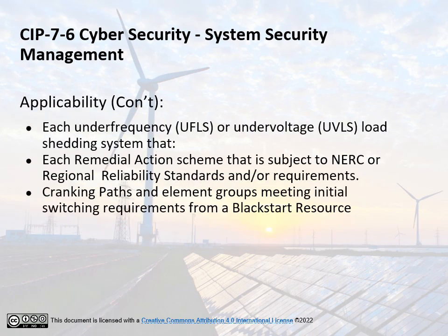CIP-007-6 System Security Management. Continued applicability: Each under-frequency load shedding (UFLS) or under-voltage load shedding (UVLS) system that is subject to NERC or regional reliability standards and/or requirements and performs automatically under a common control system without human operator initiation, of 300 megawatts or more. Each remedial action scheme that is subject to NERC or regional reliability standards and/or requirements. Cranking paths and element groups meeting initial switching requirements from a black start resource up to and including the first interconnection point of the starting station service of the next generation units to be started.